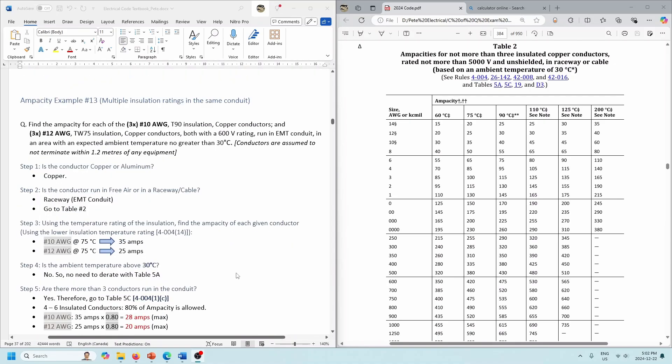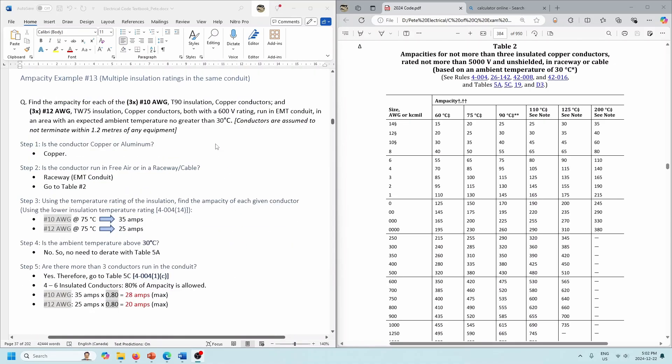So we've got the next one with multiple insulation ratings in the same conduit. In all the previous videos, we had the exact same gauge of wire and exact same insulation rating. So let's look at multiple insulation ratings in the same conduit. Keep in mind that this has nothing to do with the 80% rule, and this has nothing to do with the fact that most terminations are either 60 or 75 degree termination ratings — we're going to get to that rule in the next video.